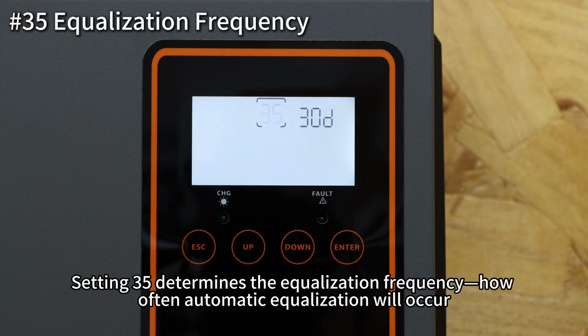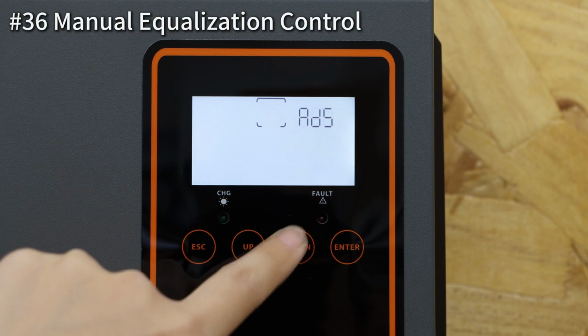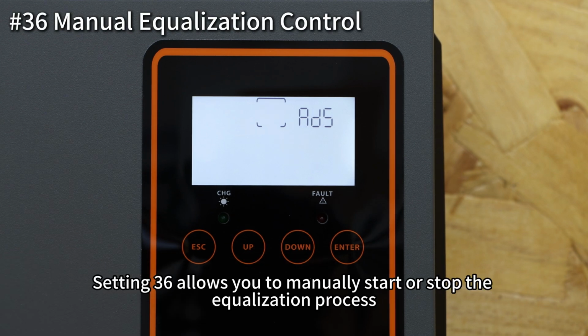Setting 35 determines the equalization frequency, meaning how often automatic equalization will occur. Setting 36 allows you to manually start or stop the equalization process.